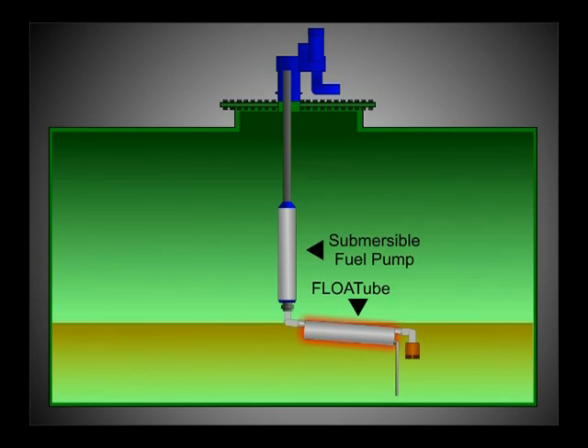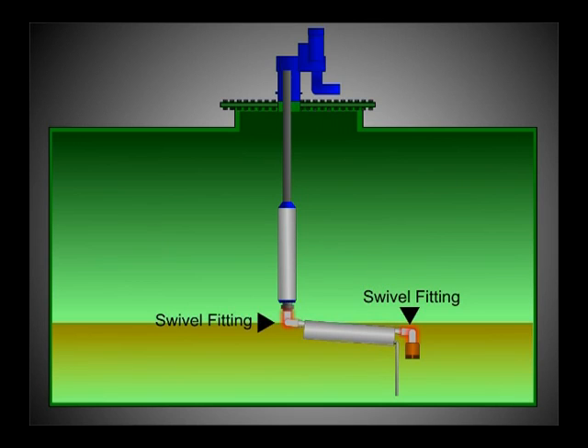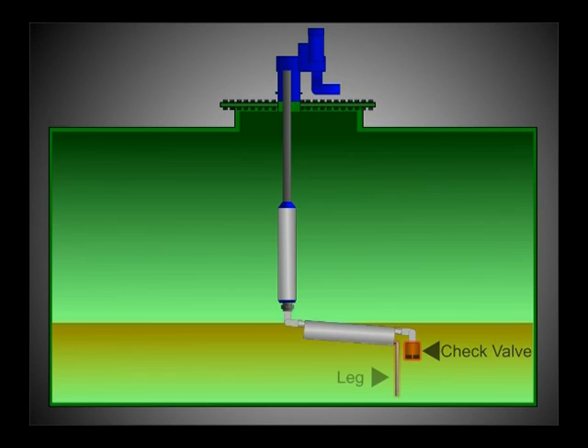The float tube allows the pickup line to float. The swivel fittings allow the float tube to move smoothly and reliably according to the level of the tank. The check valve keeps the pump primed. The leg ensures that the float tube does not bottom out in the tank.